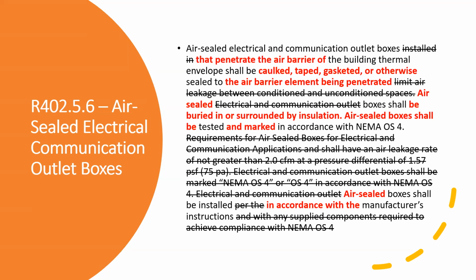in accordance with NEMA OS4. However, they've kind of rewritten some of this and said air-sealed electrical and communication outlet boxes that penetrate the air barrier of a building thermal envelope shall be caulked, taped, gasketed, or otherwise sealed to the air barrier element being penetrated. But then it says air-sealed boxes shall be buried in or surrounded by insulation. Air-sealed boxes shall be tested. So again, you have to ask your building official how he reads this. My intent is if it's manufacturer made to be airtight, then it needs to have that stamp on it.